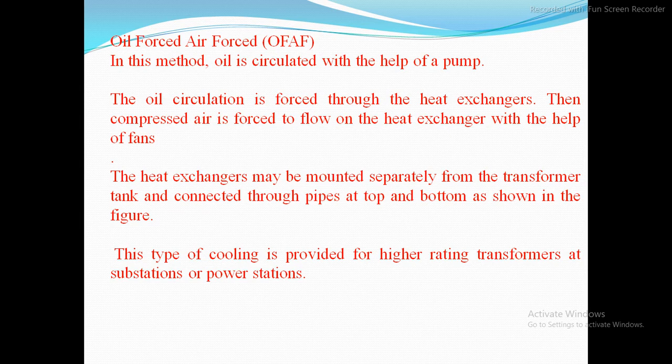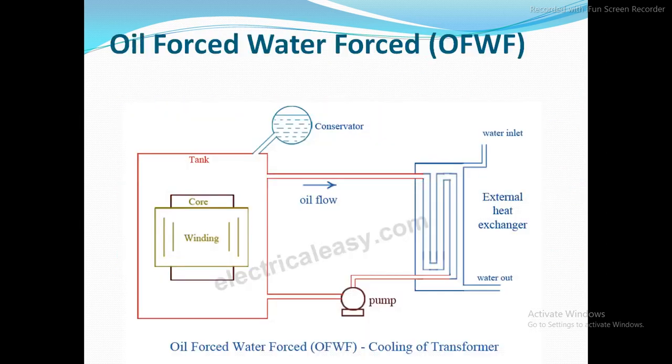I have already told you, because when natural circulation is not enough to dissipate heat, then we have to use the oil force method. So in the last, I would like to say one more method, that is oil force, water force. Sometimes air is not enough to dissipate or remove the heat from the heat exchanger, then we have to use cool water. We have to use cool water here, so that is what is used here. So you can see in the diagram, oil force, water force.